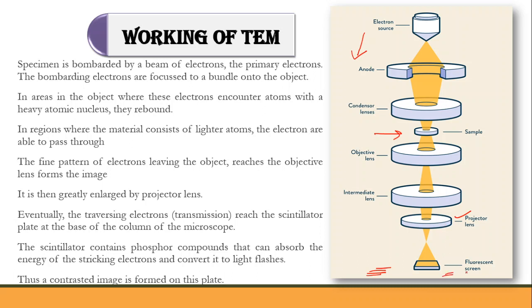The fine patterns of electrons leaving the object reach the objective lens, forming an image that is enlarged with a projector lens. Eventually, the transmitted electrons reach a scintillator plate or fluorescent plate containing phosphor compounds, which absorb the energy of the striking electrons and form a contrasted image on that plate.